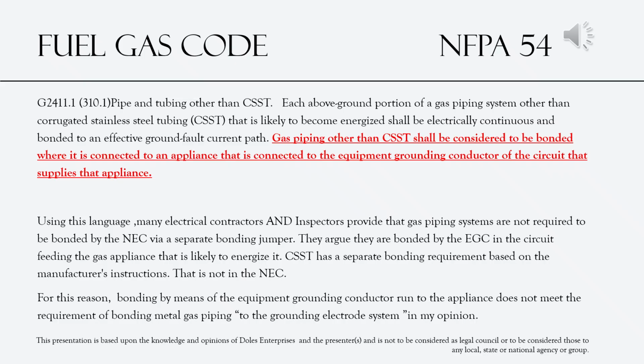Alright, that's a big question right there, right? It asks a lot. So using this language, many electrical contractors and inspectors provide that gas piping systems are not required to be bonded by the NEC via a separate bonding jumper. They argue that they are bonded by the equipment grounding conductor in the circuit feeding the gas appliance that is likely to energize it. Now, CSST has a separate bonding requirement based on the manufacturer's instructions. This is not in the NEC. For this reason, bonding by means of the equipment grounding conductor run to the appliance does not meet the requirements of bonding metal gas piping to the grounding electrode system, and that's in my opinion.